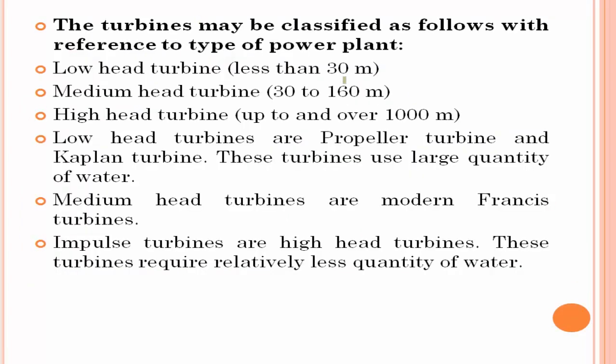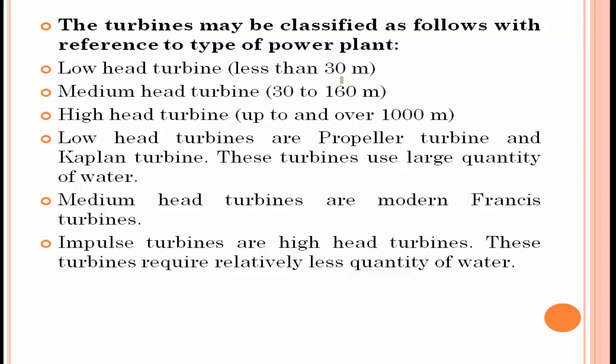Turbines may also be classified with reference to the type of power plant. For low head turbines, the head is less than 30 meters; medium head is 30 to 160 meters; high head turbine is above 160 meters or over 1000 meters. For low head, examples are the propeller turbine or Kaplan turbine, which use a very large quantity of water. For medium head, an example is the Francis turbine. For high head, an example is the Pelton wheel turbine.